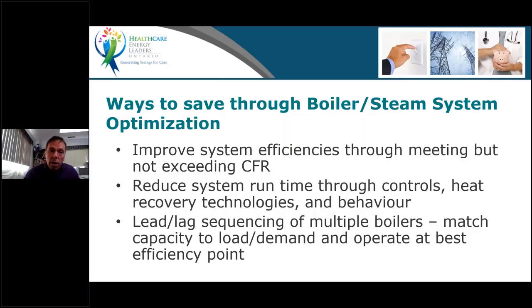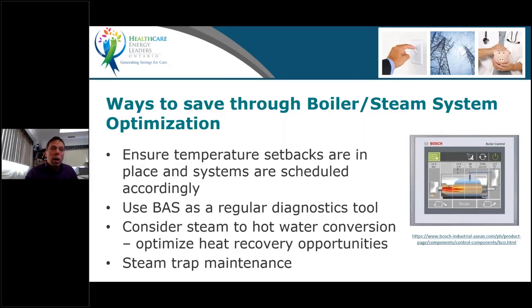You should try to synchronize the boilers as much as a turn down ratio will allow, because they're more efficient at partial load than at full load when you're talking about condensing boilers. So those are ways you can optimize. I talked about the setback. Use the BAS to do regular diagnostics, and there is the steam traps.